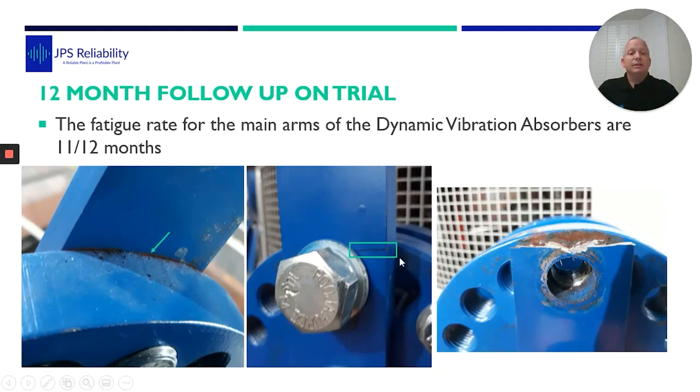And you can see there, it is cracked exactly where you would expect it to crack. So we were really chuffed. The motor had lasted more than a year. This had worked. This has absorbed the energy. Within a 12-month period, it had fatigued and cracked.